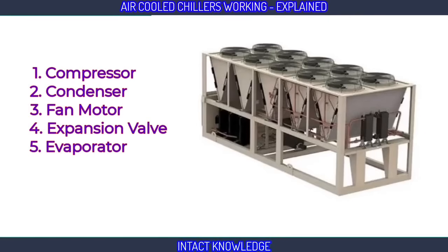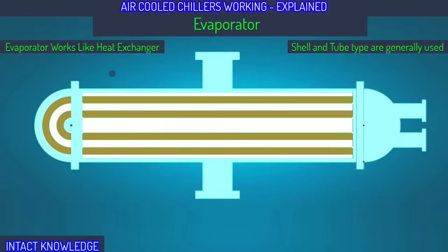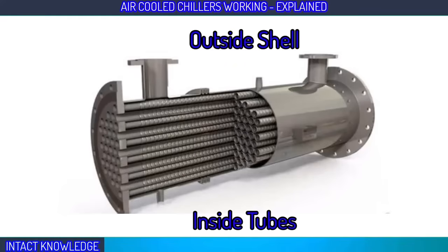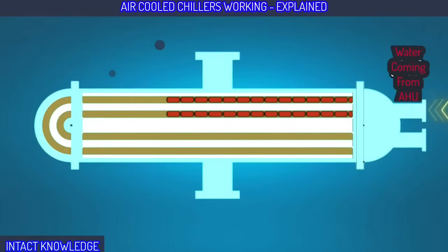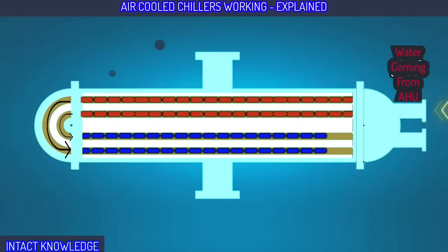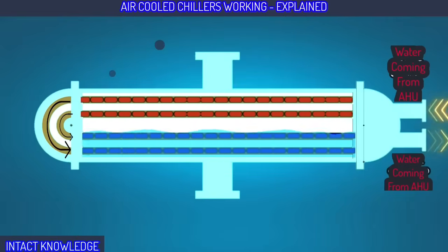As we have already said, there are 5 important equipment in air-cooled chiller. They are compressor, condenser, condenser fan motor, expansion valve, and evaporator. First, let's start from evaporator. An evaporator works like a heat exchanger. Shell and tube evaporator are generally used in chillers. Shell and tube evaporator means that the outside of the evaporator is like a shell and inside it is coils. Inside the coil, the water from the AHU travels. Refrigerant is around the coil.